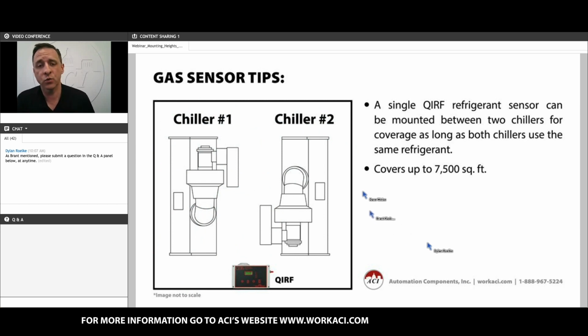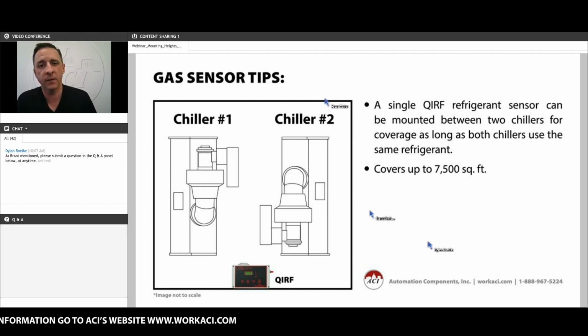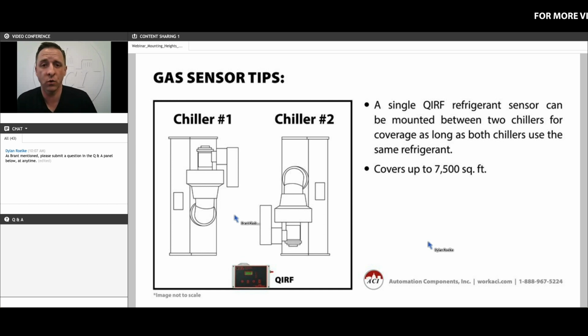Moving on to refrigerants. You can use one sensor to cover multiple chillers, assuming that each chiller uses the same type of refrigerant. So in the drawing on your screen, we would have one QIRF refrigerant sensor or monitor mounted towards the floor, because it's a very heavy gas, in between these two chillers. So you don't necessarily have to have a separate sensor for each chiller, as long as they are using the same refrigerants, and that the overall space would be less than 7,500 square feet.